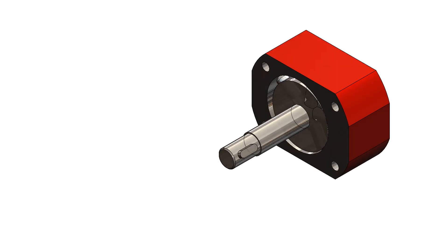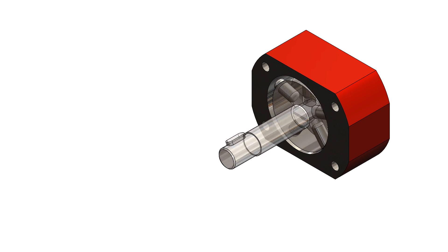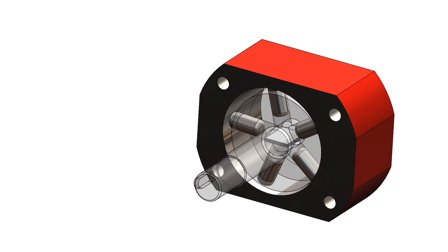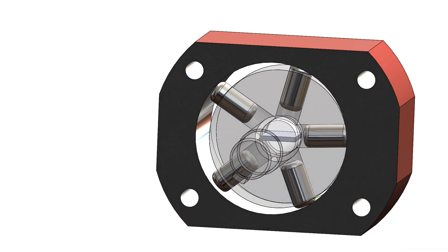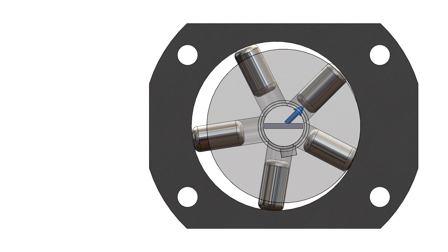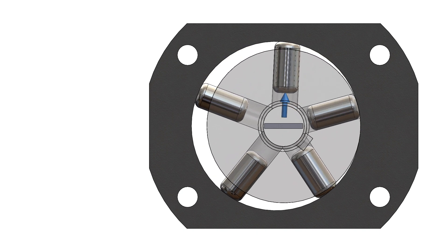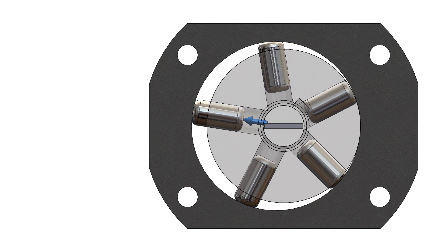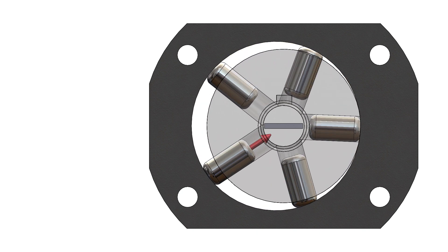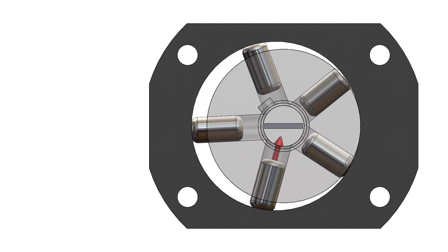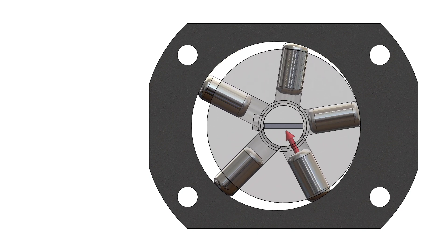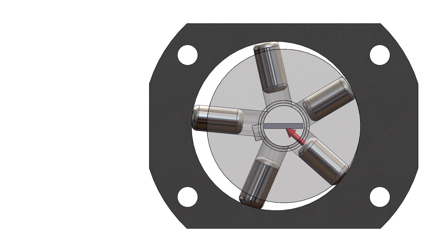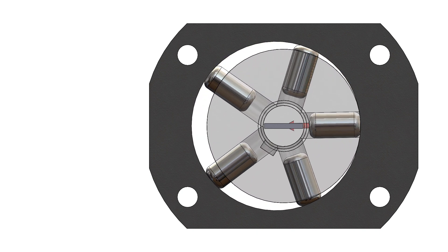The cylinders are positioned radially around the axis of rotation. The piston starts in the inner dead center with the suction process. As the shaft rotates, the displacement chamber becomes larger and fluid flows into the displacement chamber. After a rotation angle of 180 degrees, the piston is in the outer dead center, and from this point the piston displaces the fluid in the pressure channel of the pump.